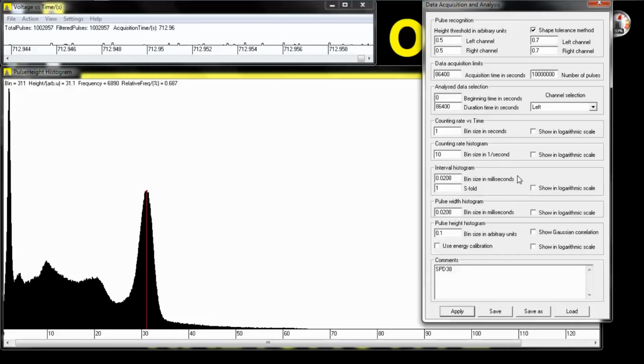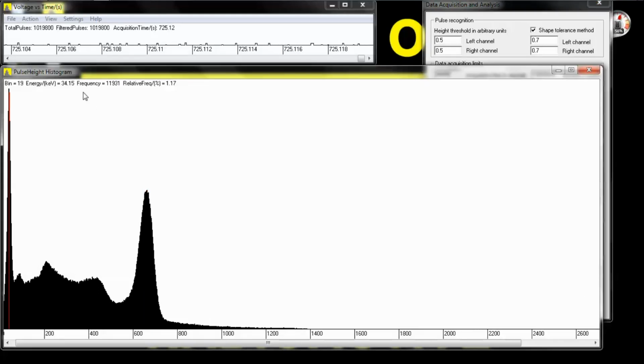Okay. Now we're going to use energy calibration. Check the checkbox and click OK. And now we are calibrated. As you can see, we expect that this will be 32 kiloelectron volts about. It's 34. Let's move over by 1. There we go, 32. And we expect that this will be 661.66, or actually 662 if you like. And there it is, 662.